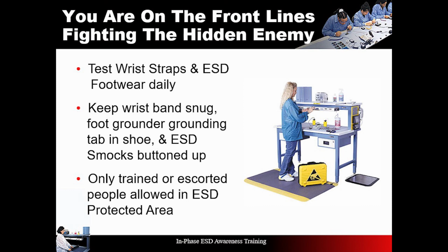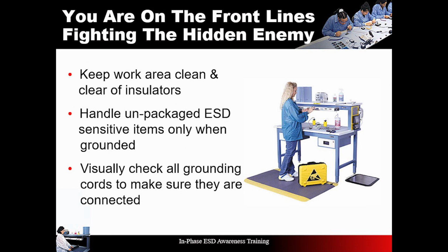ESD is a hidden enemy, and we are on the front lines fighting it. Following the guidelines listed here will help keep the enemy at bay. Test wrist straps and footwear daily. Keep wrist straps snug, smocks buttoned, and foot grounding tabs secure in your shoe. Only allow trained personnel in ESD-protected areas, and ensure that untrained people are escorted. Keep your work area clean and clear of insulators. Make sure you are grounded when handling sensitive devices.